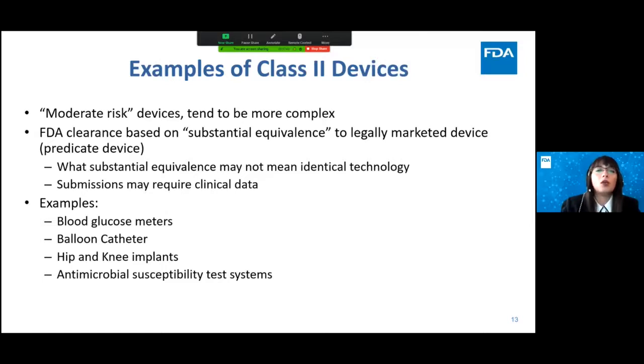And in the class 2 category, FDA determines clearance based on what we call substantial equivalence. So what we're looking at is whether the product is at least as safe and as effective as something already out in the market. And so the manufacturer, the applicant, should be able to provide enough information to make that comparison, to make that determination. One thing to note is substantial equivalence does not mean identical technology. But in cases where there is a feature that may not be well understood, it may require clinical data at that point, but not all of the submissions require clinical information.